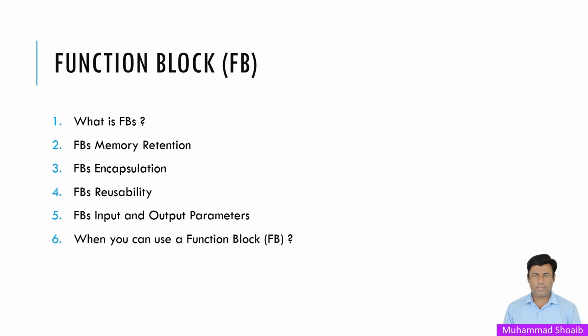When can you use an FB block? When you need to retain state information between PLC cycles, when developing repetitive logic such as controlling multiple motors or valves where each one has unique settings or states, or for PID controllers where the algorithm needs to remember previous values like the integral term to maintain proper control.